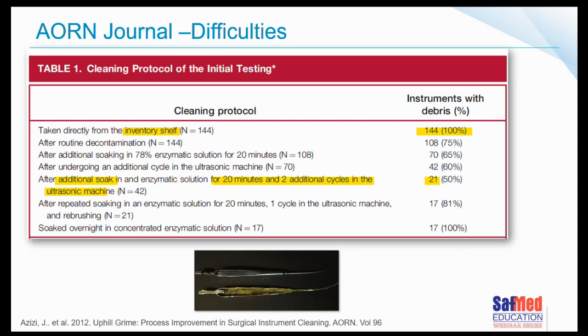So they took the 108, soaked them again, and put them through an enzymatic solution for 20 minutes, and 70 of them were still not cleaned. Then they put them in the ultrasonic cleaner again, and 42 of them were still not cleaned. They took those 42, did another soak for another 20 minutes and another 2 cycles in the ultrasonic cleaner. 17 of them were still not clean, and 17 of them never became clean.